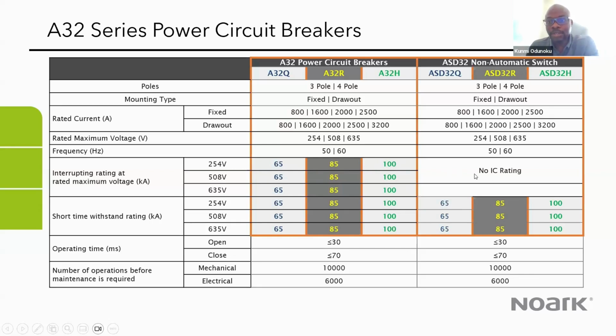If you look to my right here, under the non-automatic switch, we have no IC rating because it's not meant to interrupt the fault, since it's a non-automatic switch. For the short-term withstand, like I said before, it's 30 cycles at these values. So if you pick the A32R, which is 85 kA, it means this air circuit breaker can withstand 85,000 amps for 30 cycles. After that, it's not guaranteed what might happen to that circuit breaker. The operating time is less than 30 milliseconds for the opening operation, meaning that within 2 cycles, the breaker is able to open.